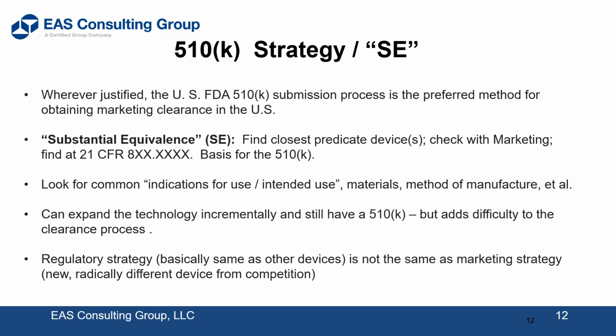And not only are they concerned with a K number that you might reference as your predicate which is not in the marketplace, so it has no use history, they're also concerned with those that are much older. Those of you who've been in industry for any length of time, and I have over 40 years in the industry, know that the 510Ks submitted in the 1980s, for example, may only be a few pages long. That's certainly not true of the 510Ks submitted today. They can be 100 pages long or more, depending on the complexity, depending upon whether electronics, software, firmware are involved, that kind of thing.